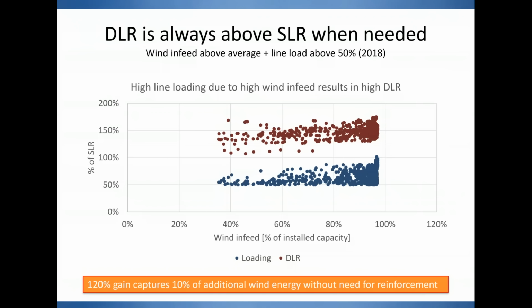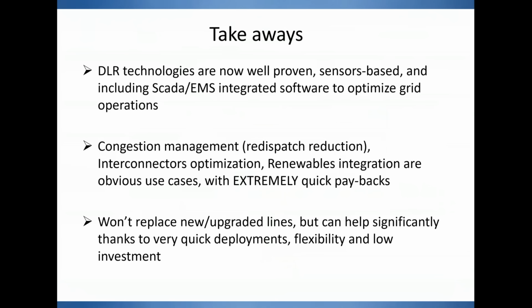So by using a correlation between the fact that the line is cooled down by the prevailing winds, and at the same time those same winds would activate wind turbines and would generate energy, you can actually, I wouldn't say avoid, but you can postpone reinforcement investments, and you can make do with your existing lines for probably a few more years than you would otherwise do, and start accommodating more wind farm connections to your grid, or avoid curtailment until your grid is structurally reinforced.